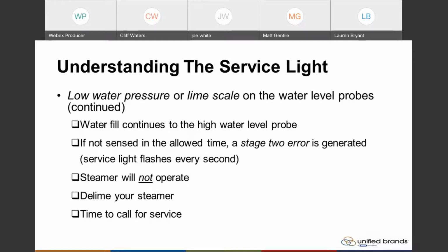And yeah, you noted that correctly. The unit will shut down at that time. The steamer will not operate. Delime your steamer. And if it doesn't come back on, it is now time to call for service. Or again, get your maintenance guys in, or if I've got maintenance guys online, you want to go in, you want to pull those water level probes, you want to take a look at those probes, make certain there's no lime scale on the probes that would not allow it to conduct in that water.